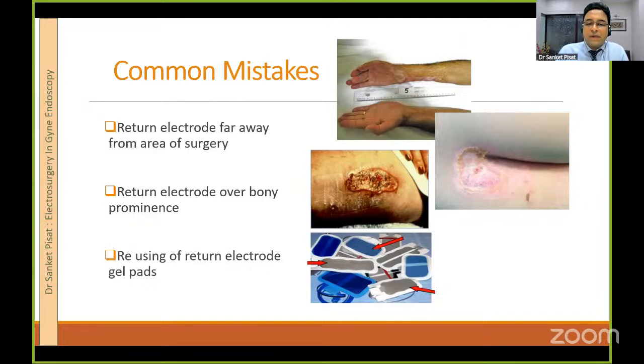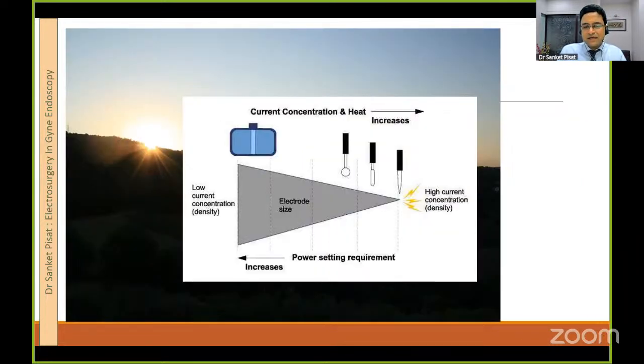Reusing of return electrode gel pads is yet another problem. And you see over here, these are return electrode gel pads. They are fantastic and they can measure the amount of current flowing back into the machine and give you an extra safety feature. But these are meant to be disposable. Once or twice reusing them is understandable, but not again and again, because it is the factory set protocol that the amount of gel incorporated in these pads is enough for the return electrode to function. If one damages this by applying excessive gel and wrapping the disposable gel pad, and uses it again and again, then the machine does not understand that the fail-safe feature has been overridden, and then you get return electrode injury. So this is the same concept again.